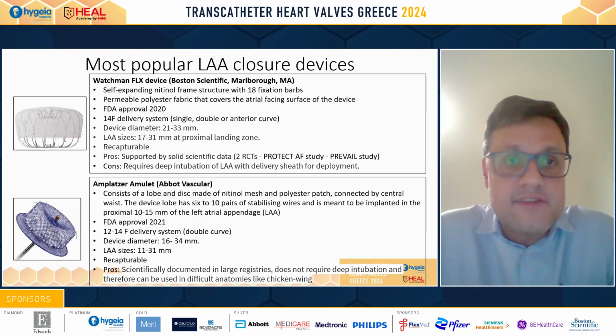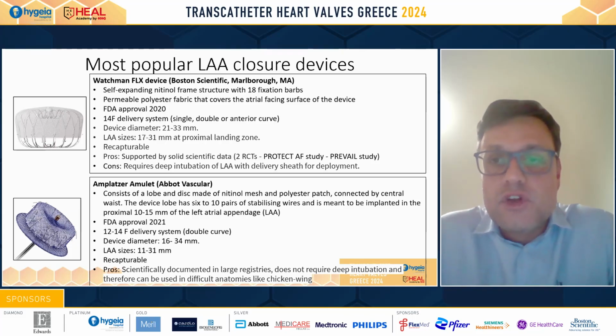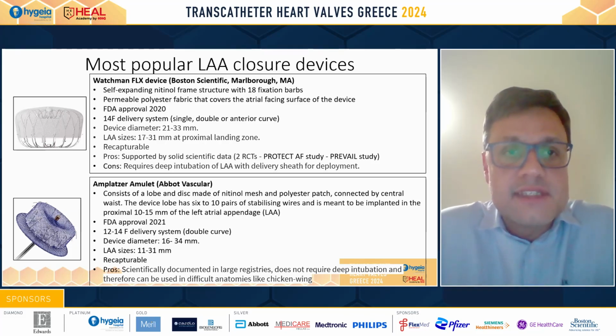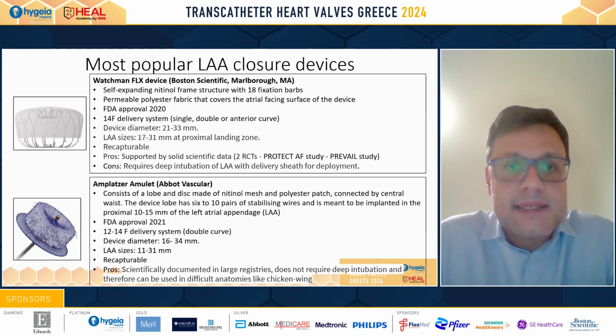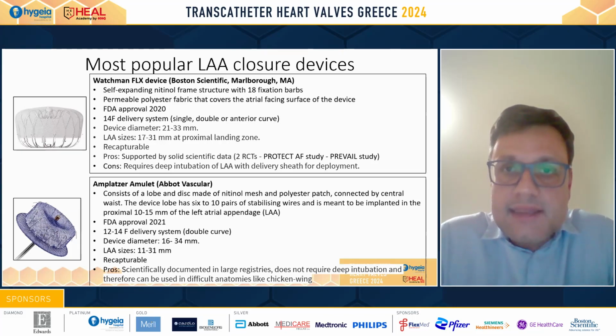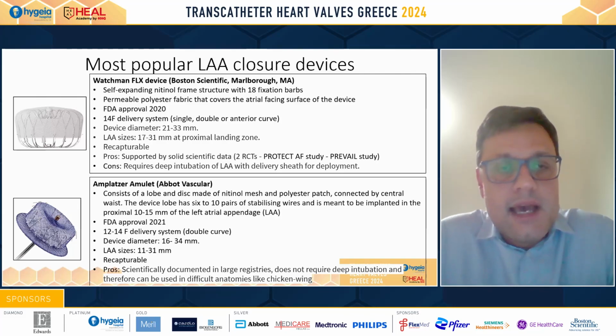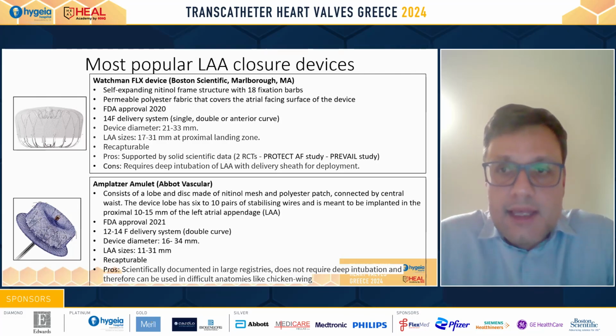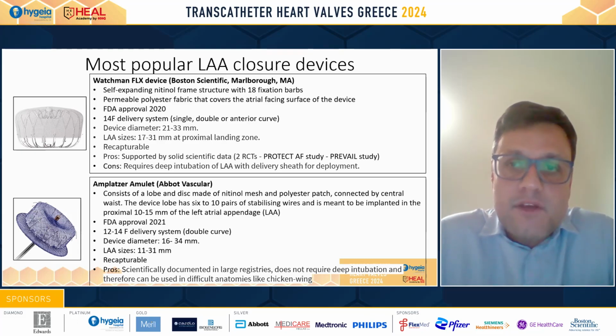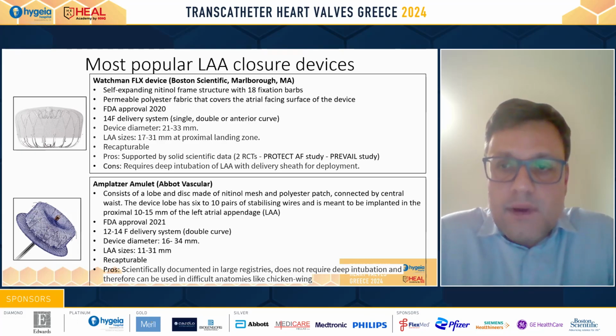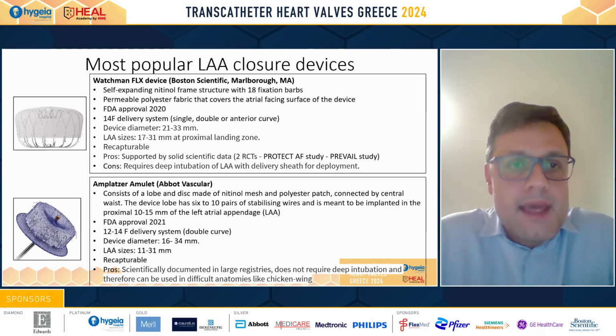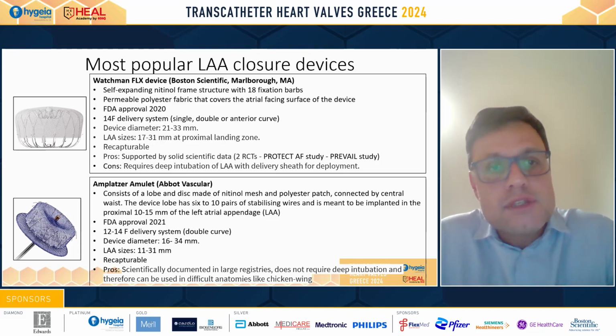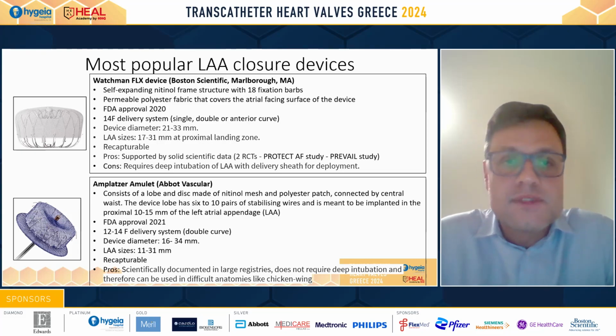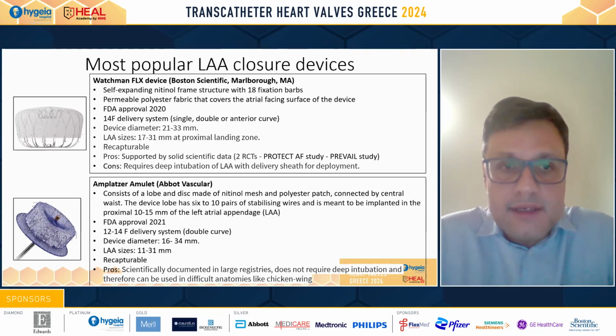There are many devices available. We will focus only on these two that have FDA approval. The Watchman FLX device, which is the evolution of the Watchman 2.5 device, is a self-expanding nitinol frame structure with 18 fixation barbs. It received FDA approval in 2020. Just to highlight, the previous Watchman device was the only one with FDA approval. The Watchman FLX can be used to close LAAs with sizes from 17 to 31 millimeters.